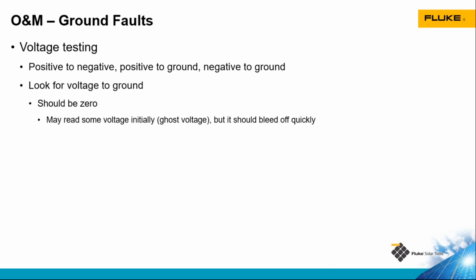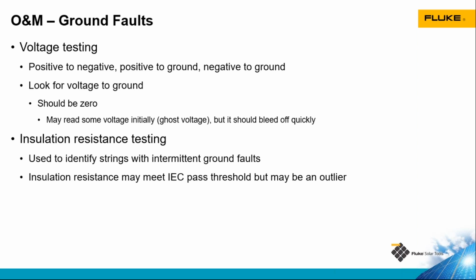Ground faults can be found in a couple ways. Inverters all have ground fault detection in them, so the inverter is going to tell you if there's a ground fault. We can do voltage testing of our PV source circuit, our string of modules, to identify the location of the ground fault. I'm going to talk about an example of that here in a minute. When we're testing between positive and negative, we should get our open circuit voltage of the string. And in modern inverters, when the array is off and the system is disconnected, there should be no voltage potential between the positive conductor and ground or the negative conductor and ground. You may get a little voltage there that should quickly bleed off to relatively close to zero.